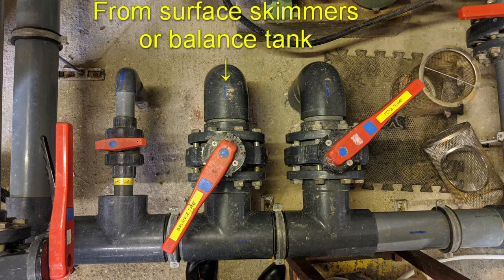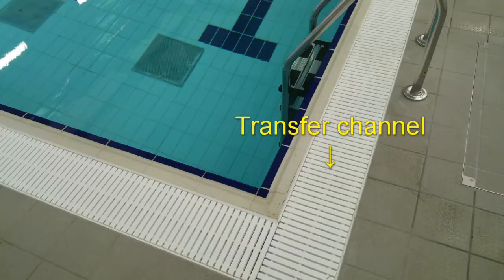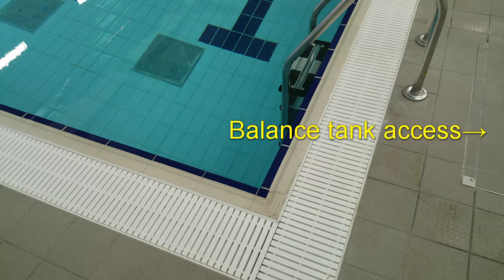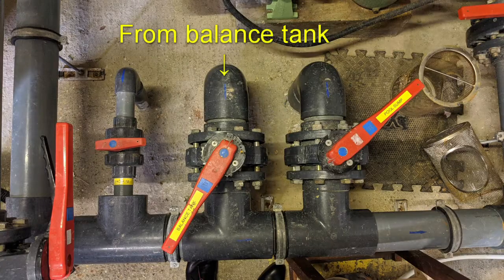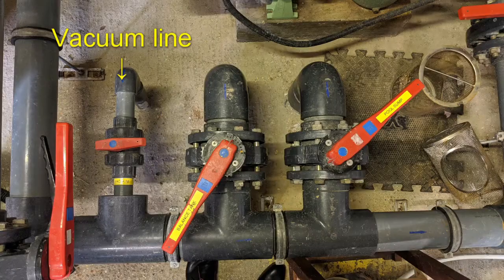If you've got a deck level pool, then the pipework will be from the balance tank, because the surface water draw-off system in a deck level pool is basically the overflow. The displaced water is flowing over into a perimeter drainage channel that drains into a balance tank, and there'll be water being drawn off from the balance tank. And so one pipe will be balance tank, one pipe will be the base of the pool. You might see a smaller bore pipe as well, with a closed valve.